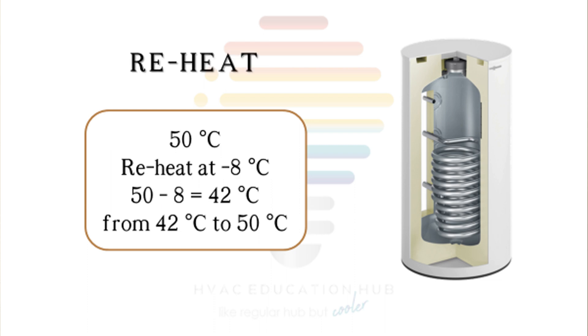We will never go below some degree Celsius. For example, if we put reheat temperature at minus 8, our set point is 50. When water drops below 42 degrees Celsius, our heat pump will start the reheating process again.